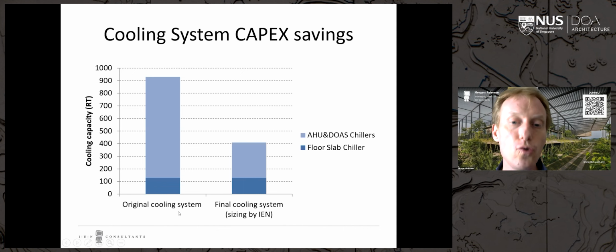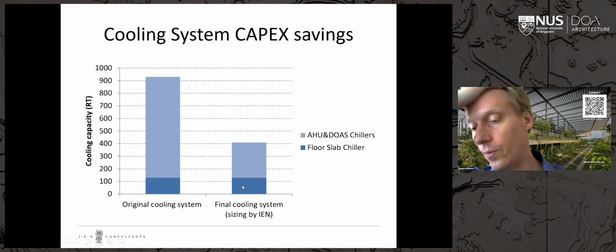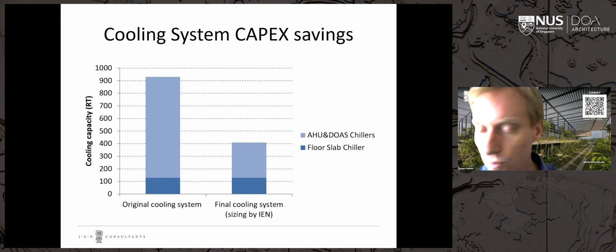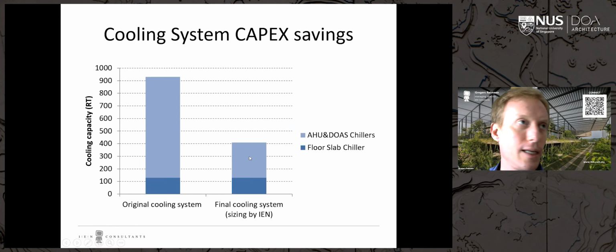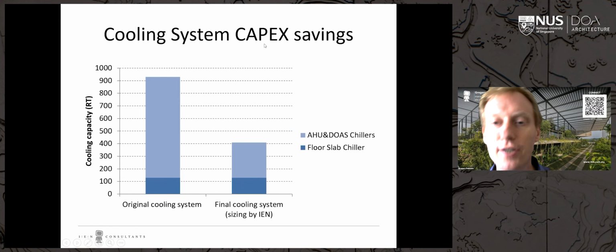The original cooling system proposal from the mechanical engineer was more than 900 refrigerant tons of cooling. We said that's too high. Of course, we did the detailed simulations, and we also had readings done from the old factory, so we knew approximately how much heat was generated by this manufacturing equipment.